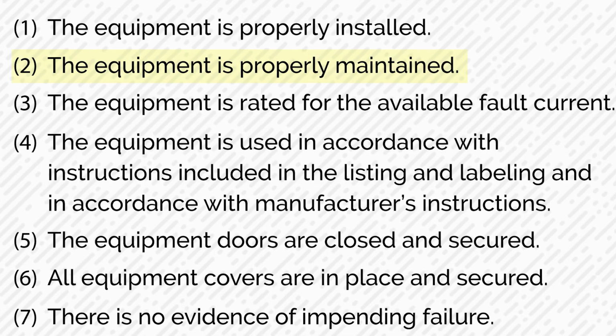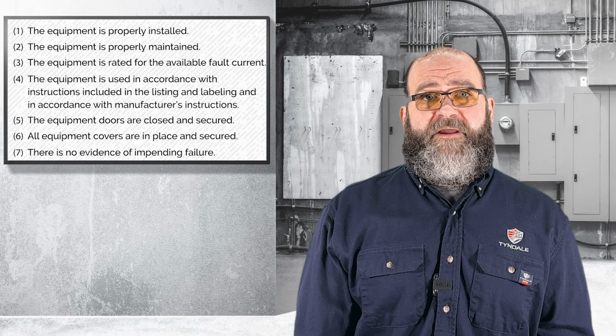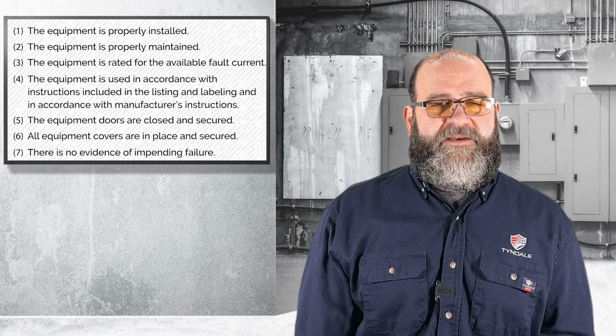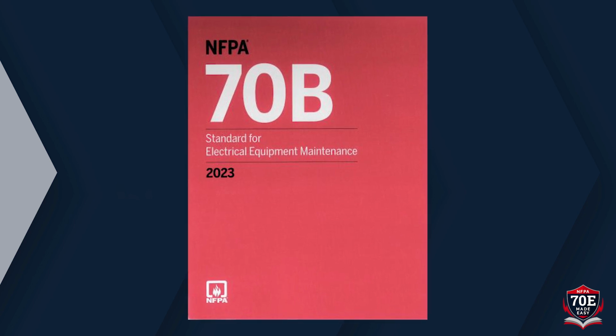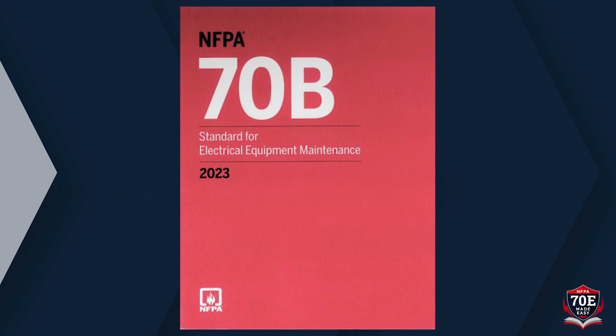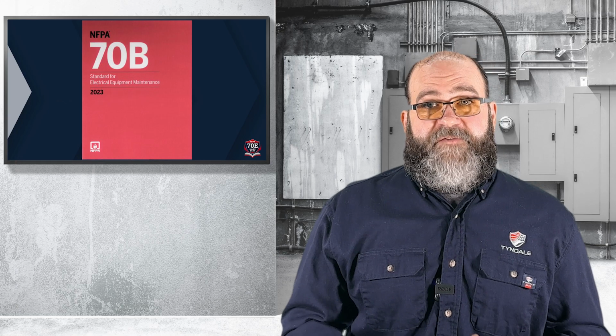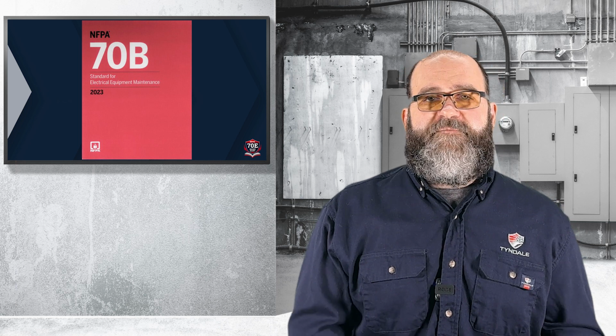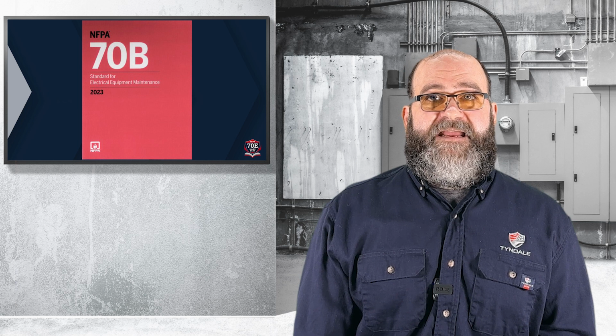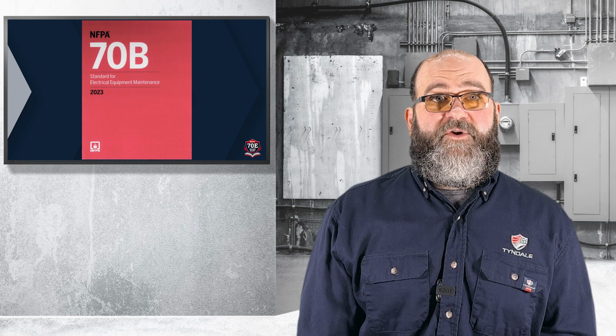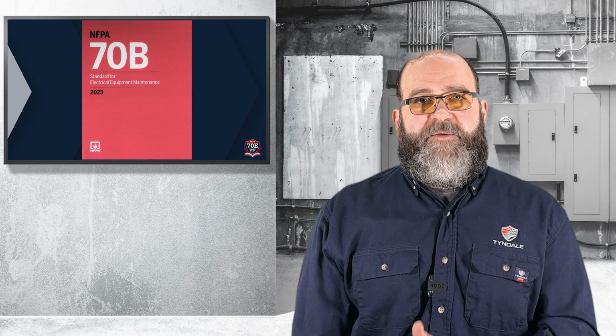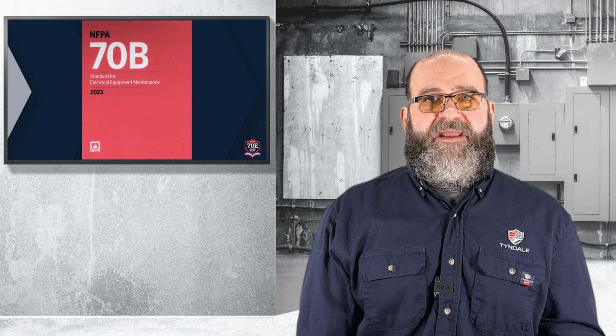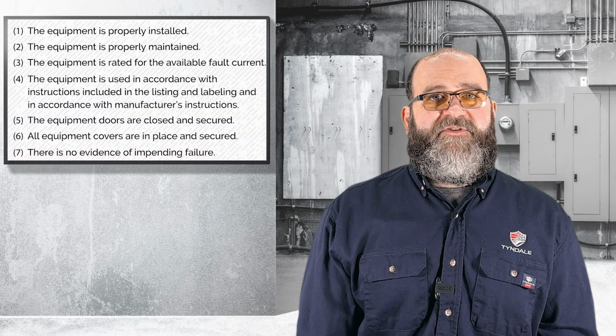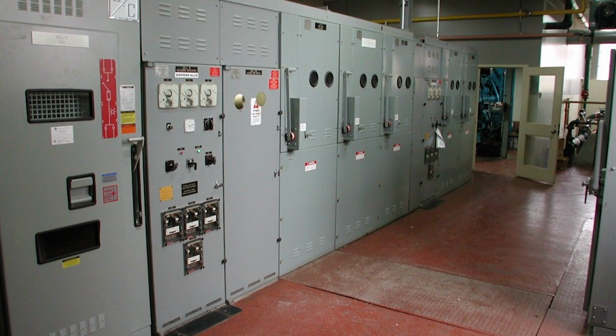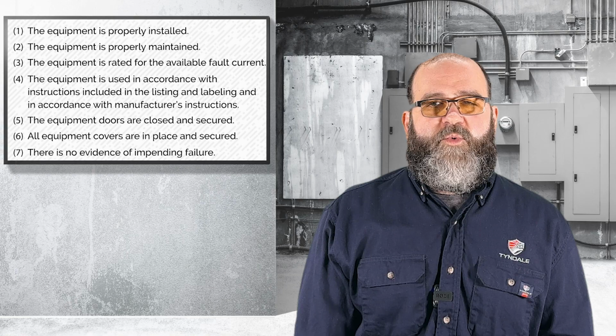For the sake of time, I just want to hit on number two, which was about your equipment being properly maintained. This is only verified by having an electrical maintenance program. How many people have an EMP, an electrical maintenance program? The 70B just became a standard in January of 2024. It spells out that you're going to need an electrical maintenance program. You will need to be very familiar with the 70B, which spells that out, unless you have manufacturer's instructions that do. That's right, I did say a standard. It won't be long before OSHA not only asks you for your electrical safety program, your ESP, but if someone gets injured, they're going to want to also see an EMP, that electrical maintenance program. As an electrician that's spent over 20 years working on equipment, I can tell you with certainty that 99% of the equipment I've seen out there was not properly maintained.